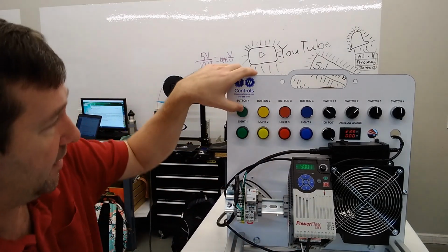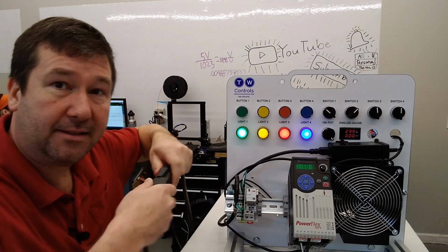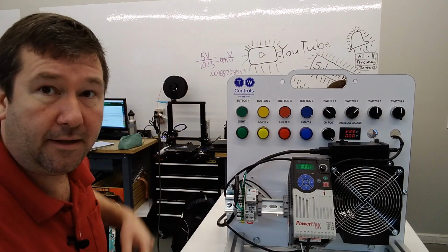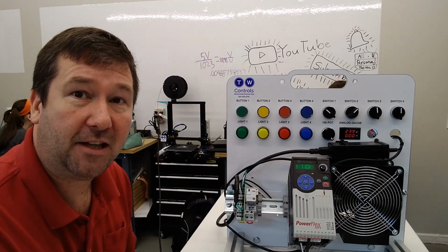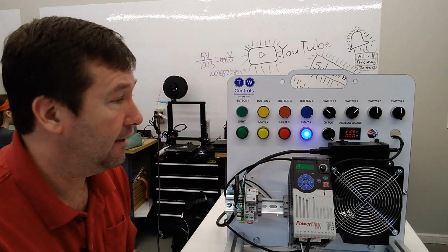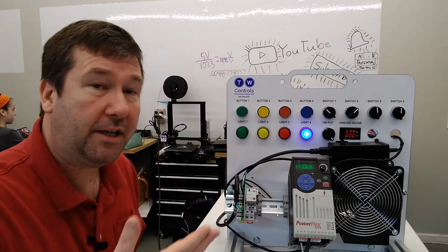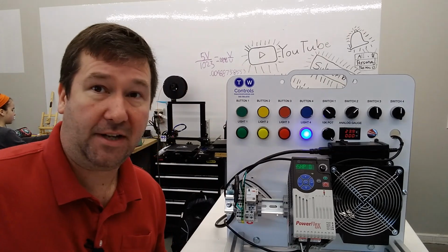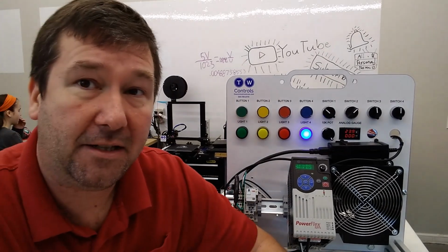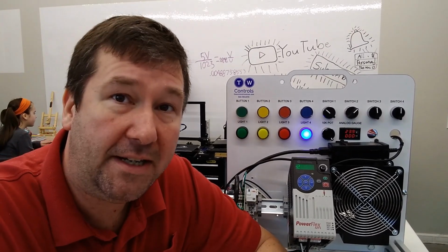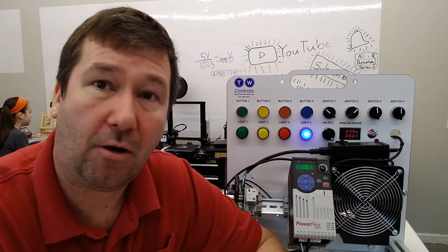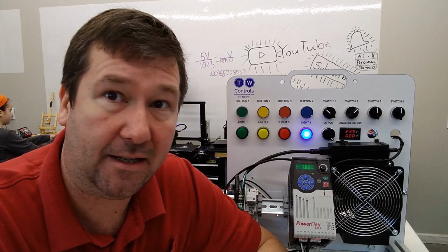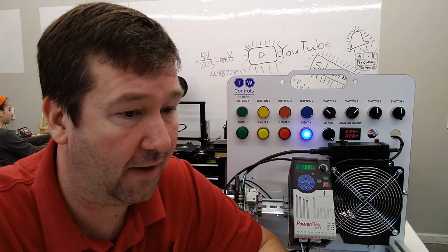But now let's press our green button and let's unplug our power. Then we'll plug our power back in and we'll wait for the PLC to come back online. And only the blue light is going to come back on. And you need to make sure you understand this part. And that is because of what we call pre-scan conditions. And these hold true in Connected Components Workbench the same as they did in RSLogix 500 and Studio 5000.